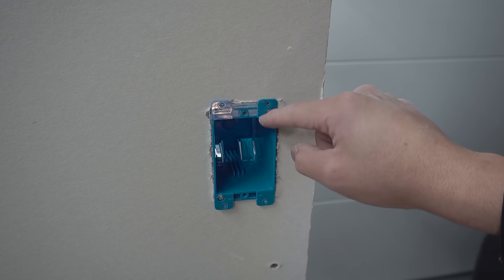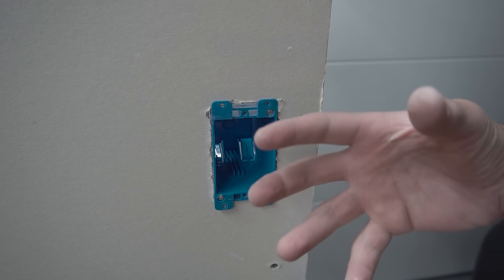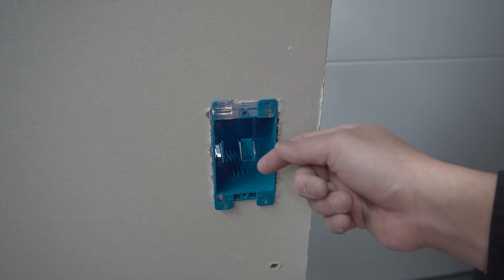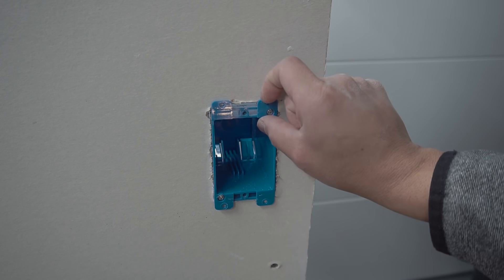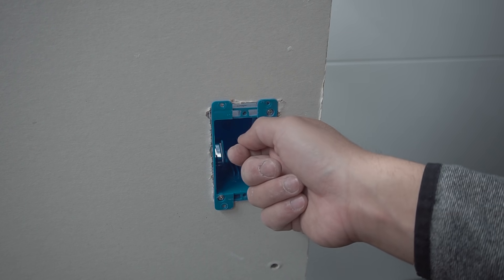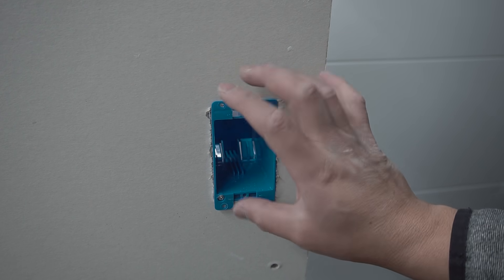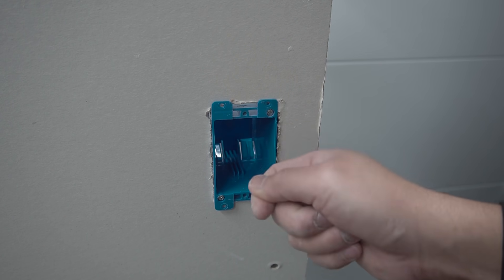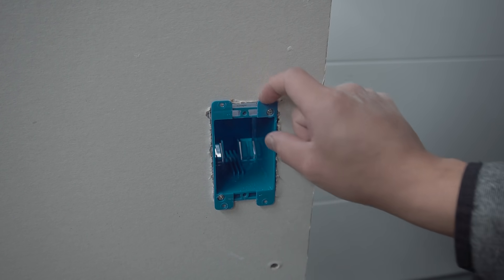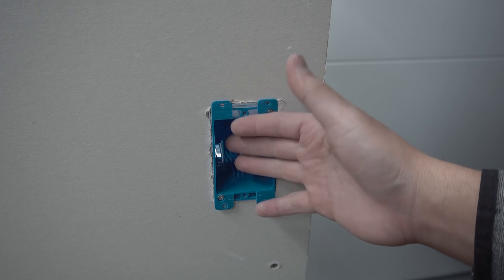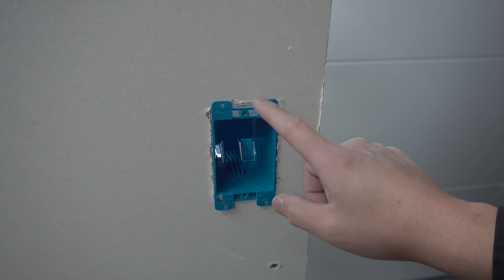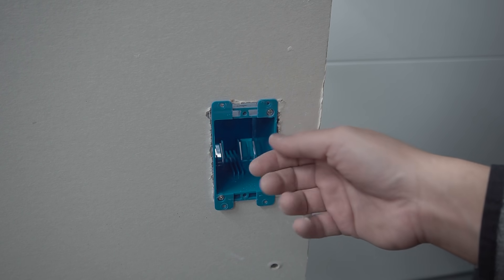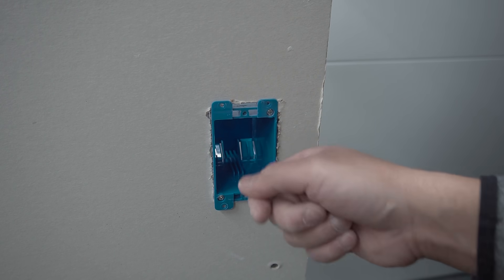This Old Work J-Box is only good, for my opinion, for switches. Because if you're using this with electrical outlets, this thing is not that strong in my honest opinion. And the longer, the more time you use this, especially if it's in a high traffic area where you're going to be using this to plug in and out a lot, this will tend to get loose over time and it will not stay in place. So I highly suggest that you use this type of J-Box on switches where you don't need to pull in and out any plugs.